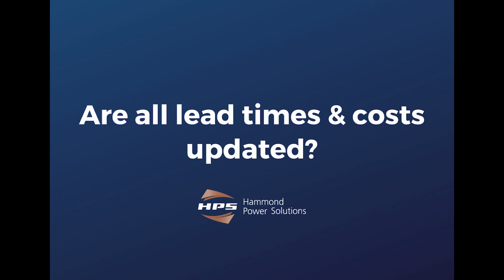Possibly. I mentioned that lead times for liquid transformers are approaching, in some cases, a year, and we've even seen 2 years. Could you get a liquid filled transformer in less than that? Absolutely. Depends, again, on the specifications and the manufacturer.